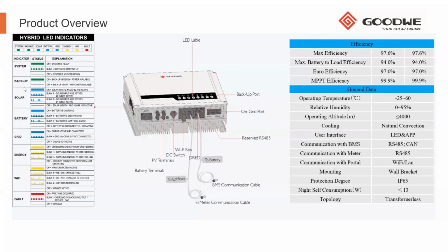On the side of our inverter, we do have the LED indicator. This can also be found in the manual. Should you have any problems with the Wi-Fi, the first point is always to look at the Wi-Fi LED to see what it is telling us. We can follow the different steps in the fault finding to know exactly: is it not connected? Is there a server problem? The fault light is another light that we pay a lot of attention to. If it is blinking, that means the inverter has overloaded. If it is constantly blinking, it could be in an overload state and waiting for the overload timer to count down.